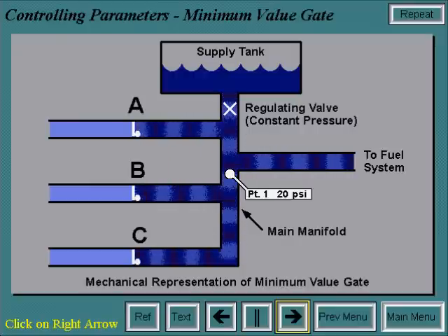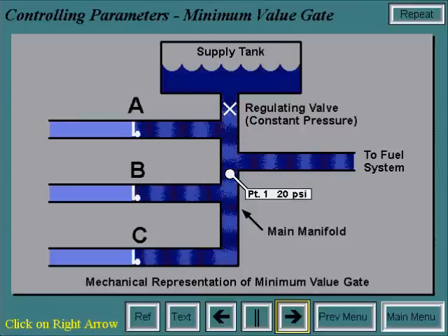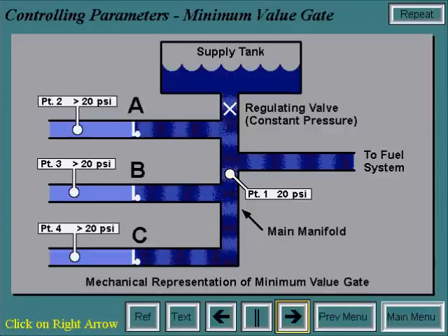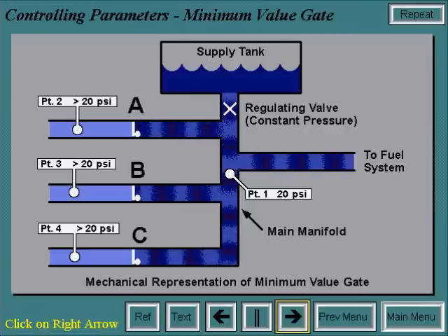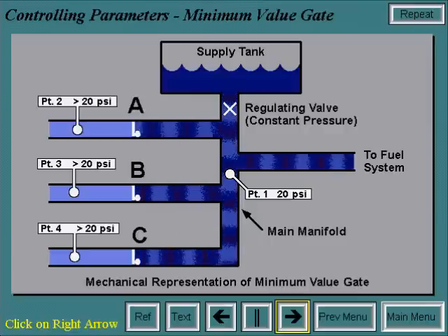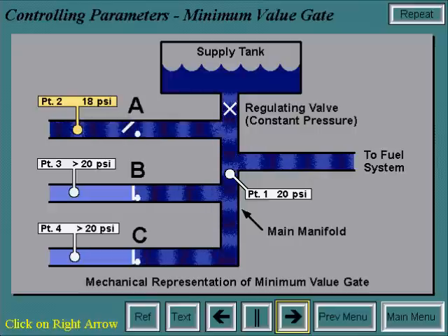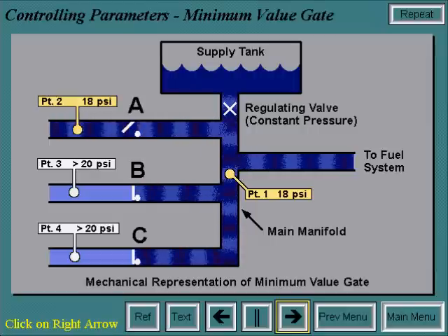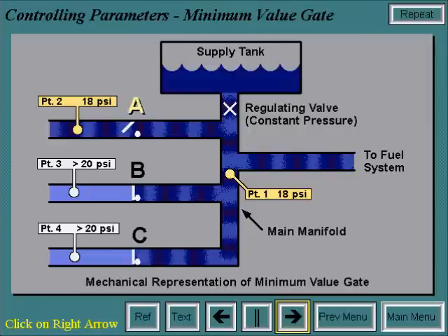For example, the pressure at point 1 is considered constant at 20 psi. If the pressure at points 2, 3, and 4 are higher than 20 psi, then there will be no control of the pressure at the main manifold. If the pressure at point 2 decreases to 18 psi and the pressure at points 3 and 4 remain the same, then the pressure at the manifold will be brought down to 18 psi and system A is controlling.